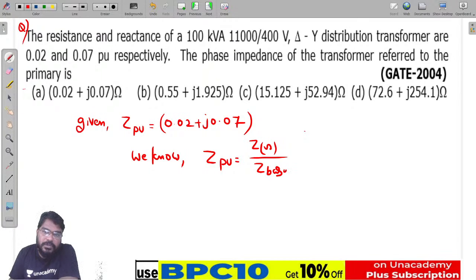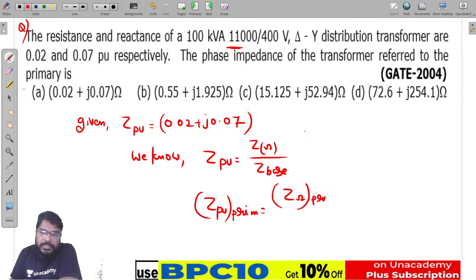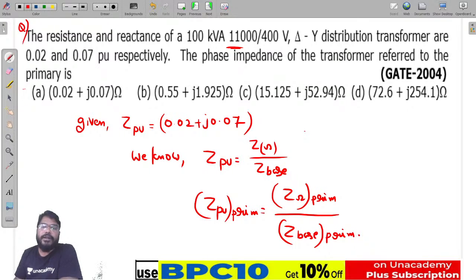So we required Z per unit referred to which side? Referred to the primary side, that is the 11 kV side, the high voltage side. So Z per unit referred to primary side is equal to Z in ohms referred to primary side divided by Z base referred to primary side. All our primary side is required, so now calculate and you will get an answer.